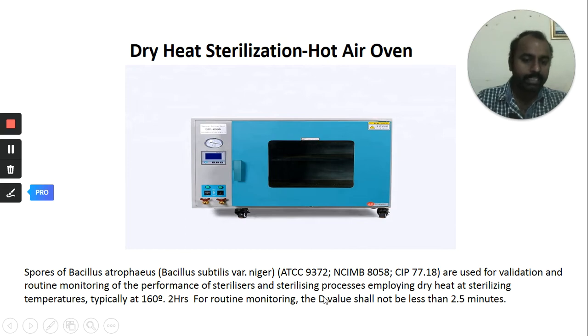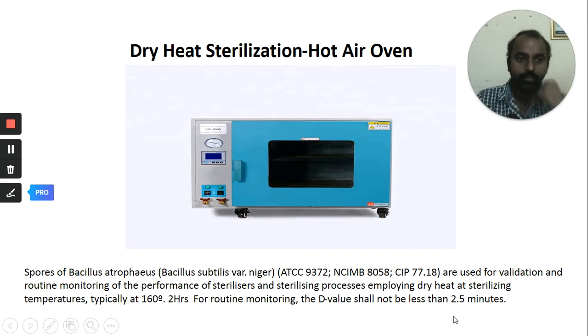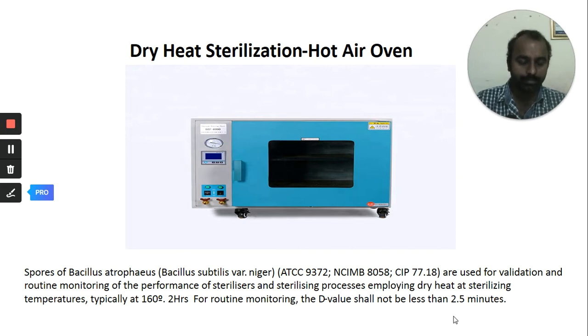To validate dry heat sterilization performance, the biological indicator used is spores of Bacillus atrophaeus (Bacillus subtilis var. niger), used for validation and routine monitoring. For a typical sterilization at 160°C for two hours, the D value shall not be less than 2.5 minutes — meaning a 90% or one-log reduction of microorganisms by a factor of 10. This is fundamental to dry heat sterilization.